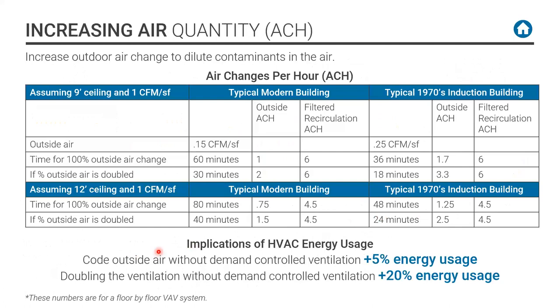So let's talk about air changes in a building. And this is an important slide, and I'll simplify it. A modern building today, if you follow the ASHRAE codes and you bring in about 0.15 CFM per square foot, it takes 1 hour to completely change the air. That means that you bring in 100% of the outside air in a 60-minute period. But it goes back to the air handling unit. It's recirculated 6 times an hour. So think about it. The air goes back and forth to the air handling unit, continuously being filtered 6 times, but you're only bringing in fresh air completely once an hour.